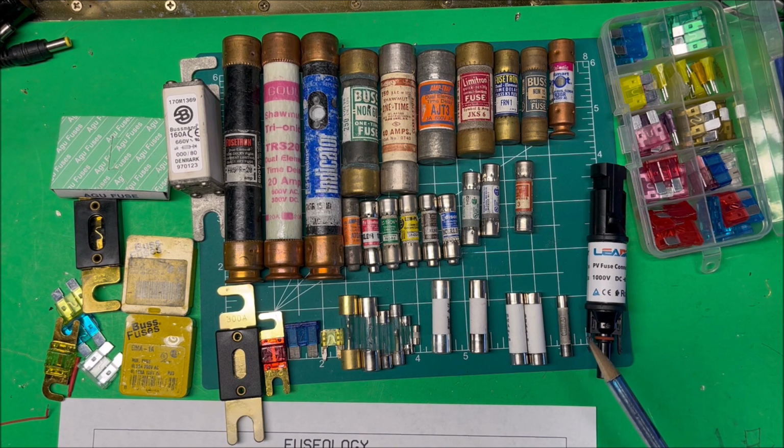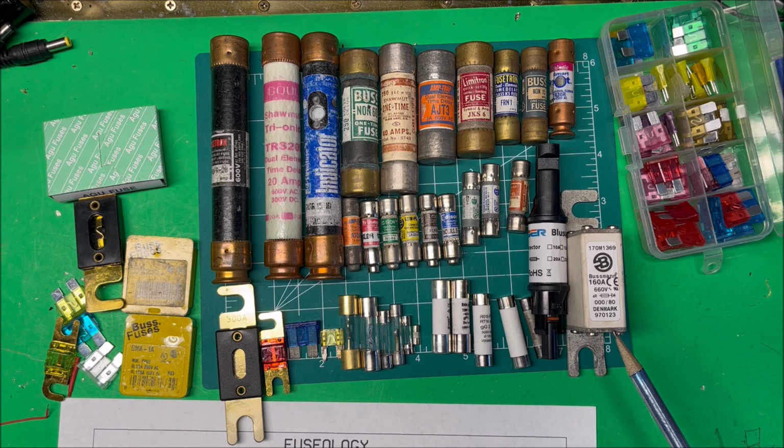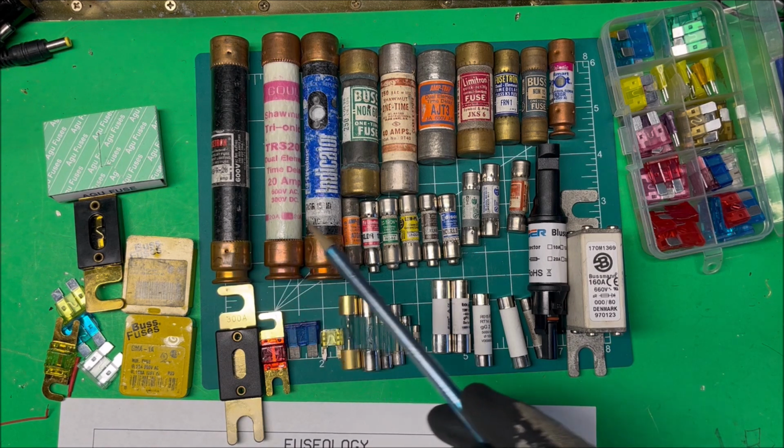And this one here is a fuse that goes into a VFD drive on a motor, and you can see the semiconductor fuse in there. It has a little diode symbol. There's no diode in here. It's just telling you that it's good for a semiconductor, and it's the AR, so it's short circuit protection. These are expensive fuses. They're about $170, all these things. These are $30.